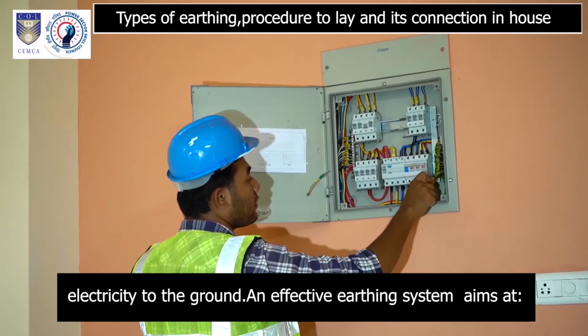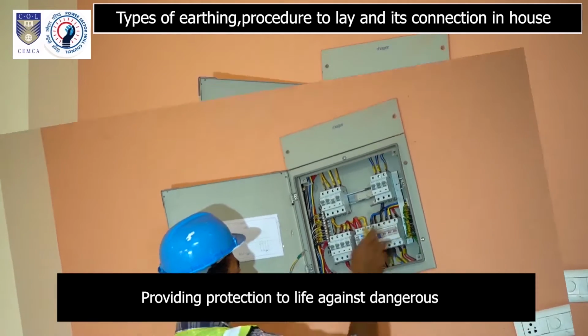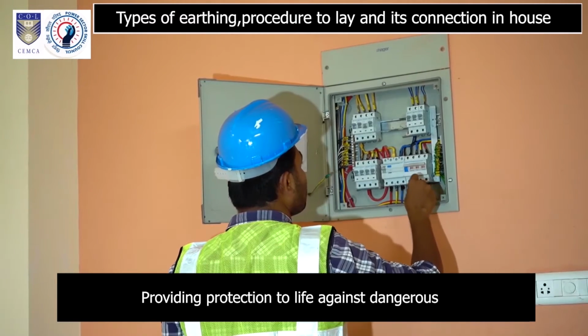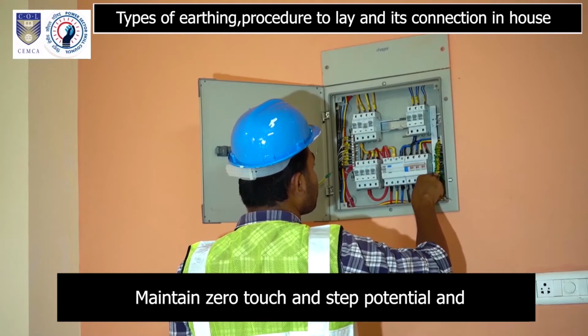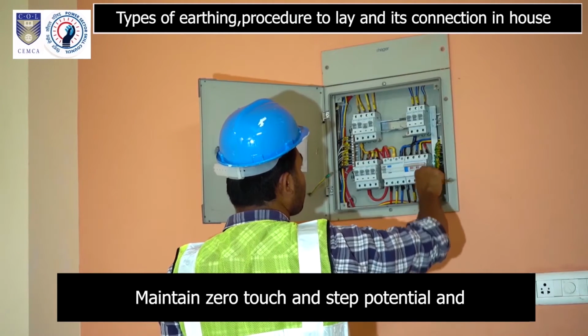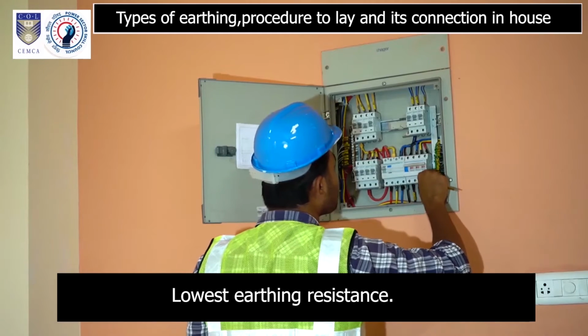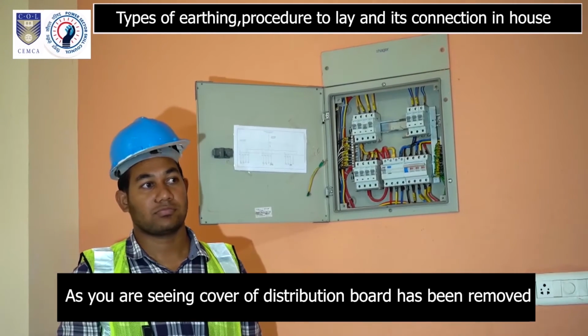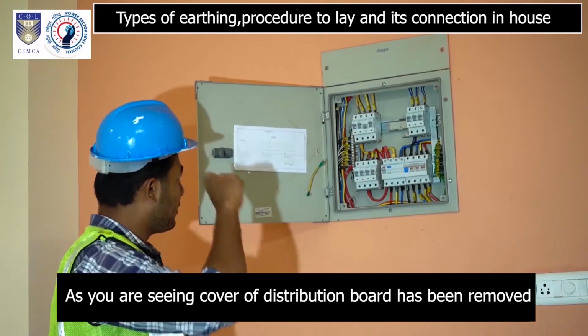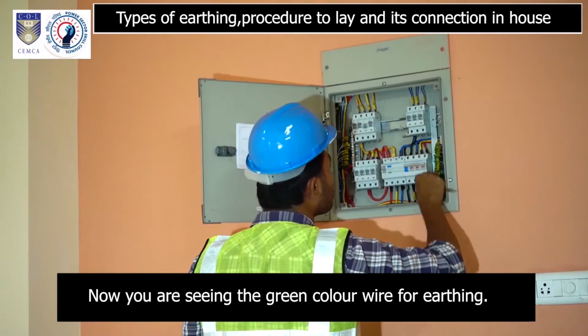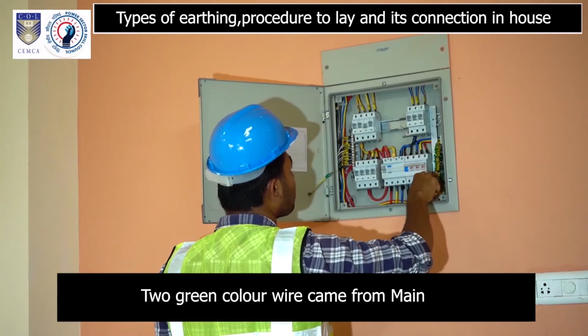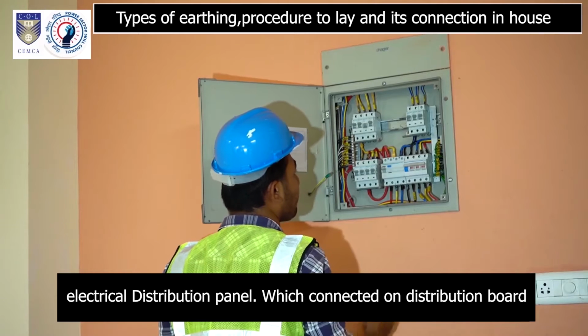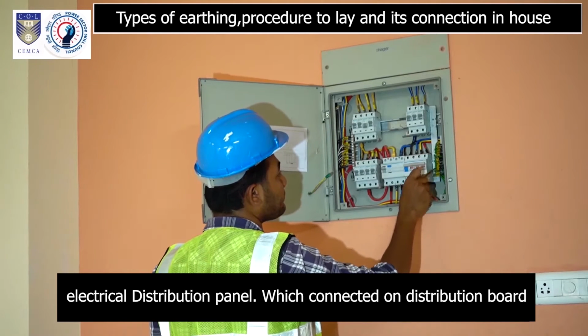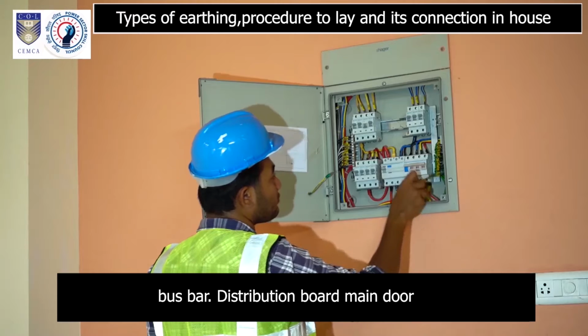An effective earthing system aims at providing protection to life against dangerous potentials under fault conditions, maintaining zero touch and step potential, and lowest earthing resistance. As you are seeing, the cover of the distribution board has been removed. Now you are seeing the green color wire for earthing. Two green color wires came from the main electrical distribution panel, which are connected on the distribution board earthing bus bar.